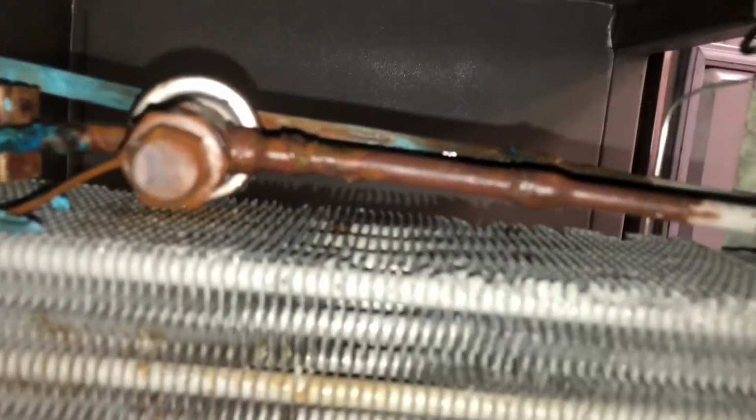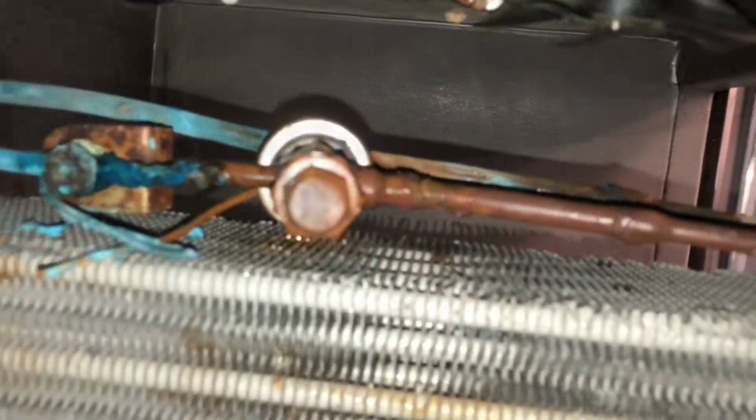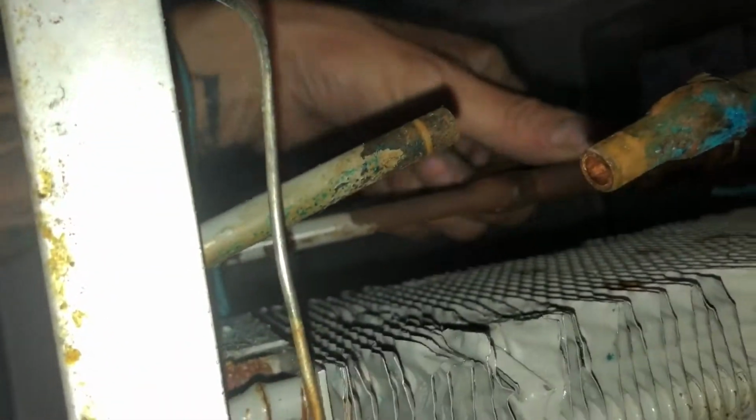So that'll come right out and all the new ones can go right in. The evaporator's identical, so everything's going to line up nice, it looks like. Around this other side, this is all free. The TXV and the solenoid, that's attached to the old piece on the evap, so you can just pull that out. This one here I cut at the little swedge fitting there.